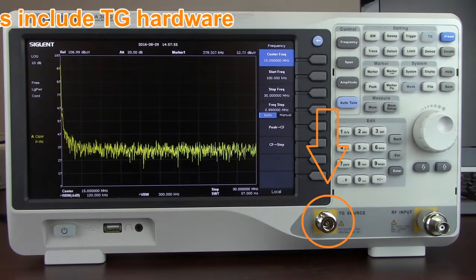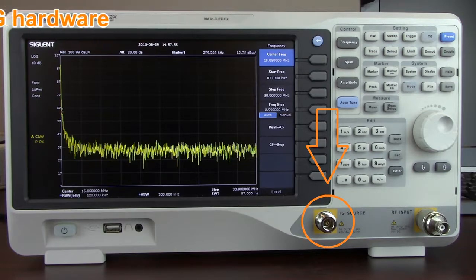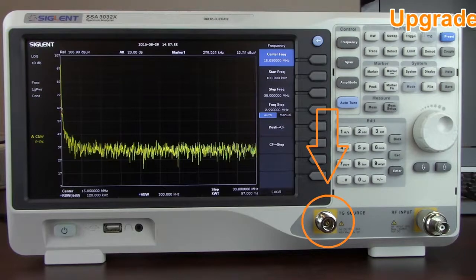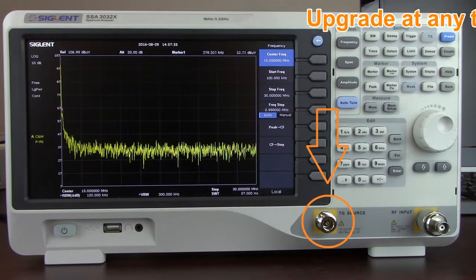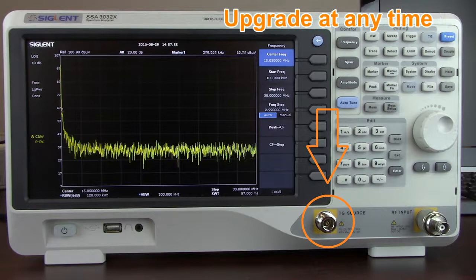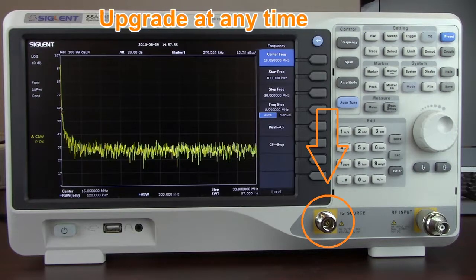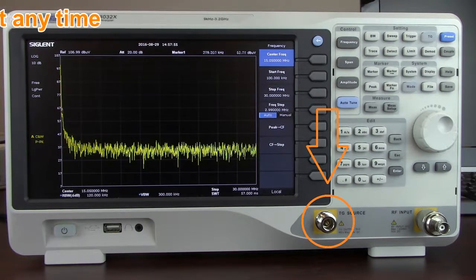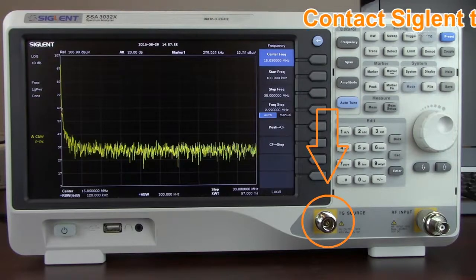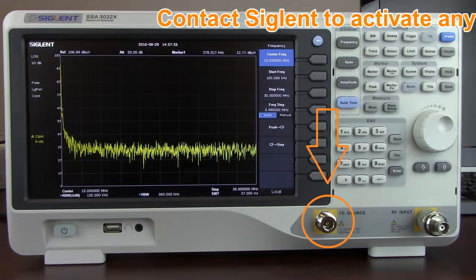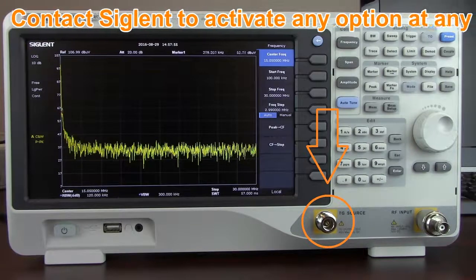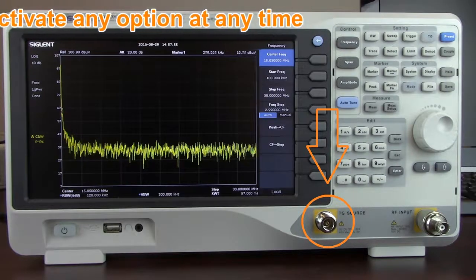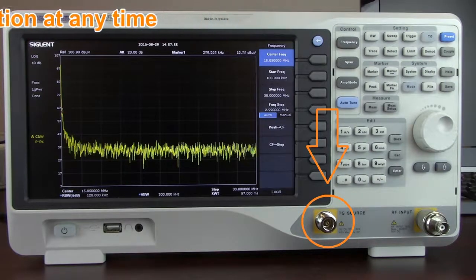To activate the TG option on the Siglent SSA 3000X, all you have to do is call your nearest Siglent office or distributor, purchase the option, and enter the license key. Unlike many analyzers, the TG also operates to the maximum frequency of the instrument, not just to 1 GHz. So if you have a 2.1 GHz unit, the tracking generator operates up to 2.1 GHz. That makes the TG option even more powerful, giving you a full bandwidth capability or full frequency span capability to test your passive and active devices.